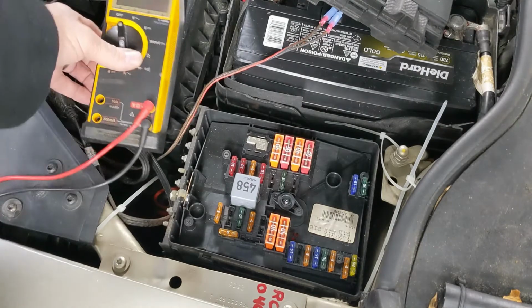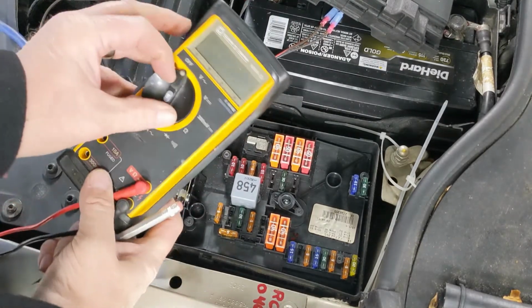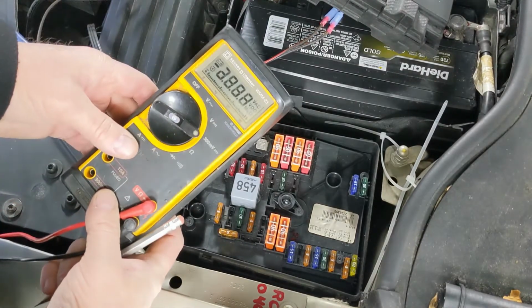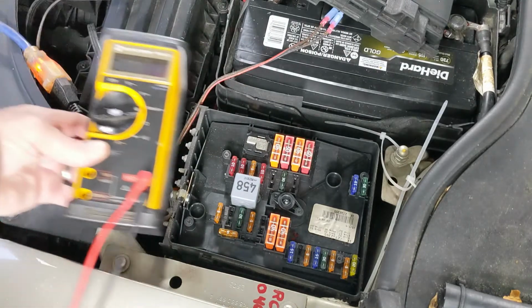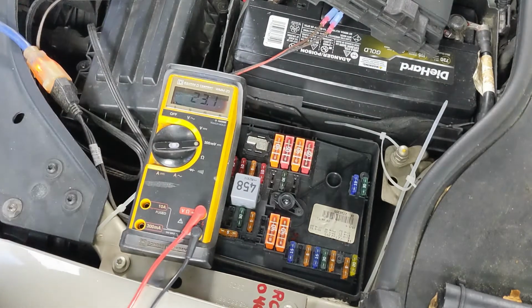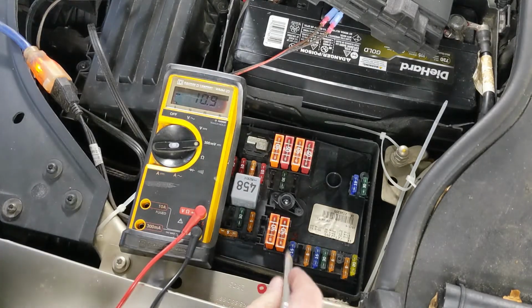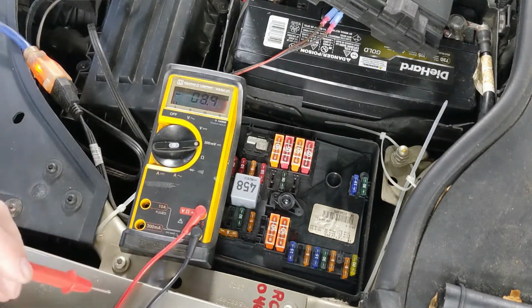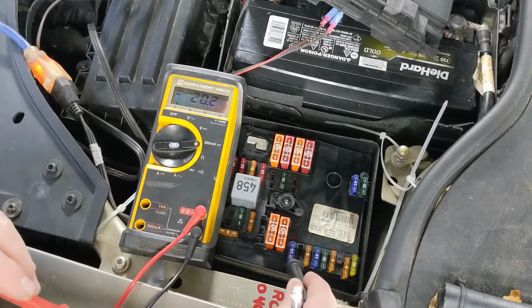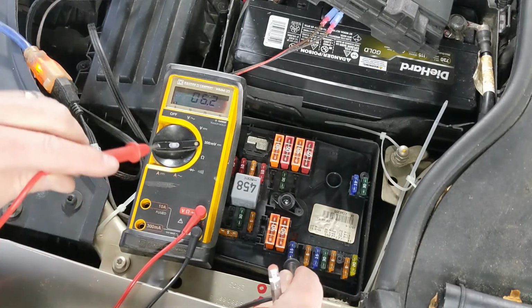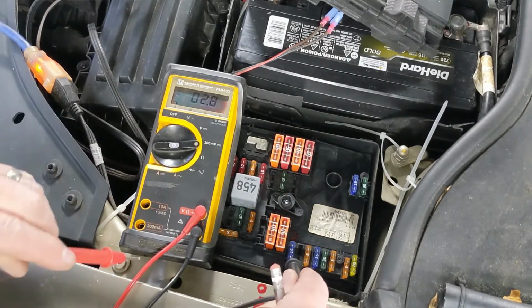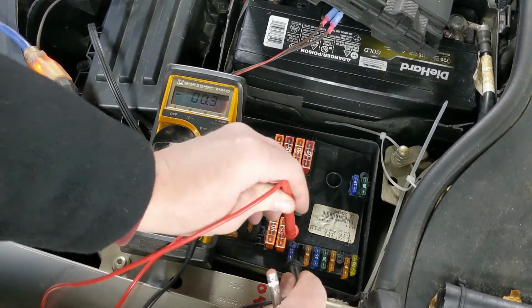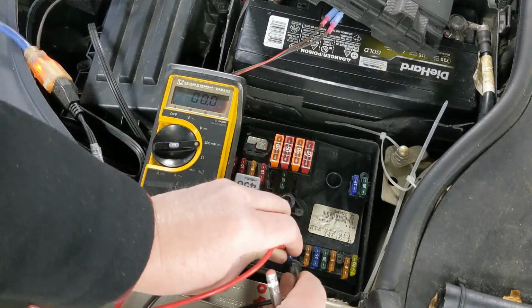So what I do is I have a voltmeter here, and I set it to the millivolt scale. I'll take this one of the fuses where I was reading a large amount of current on it. You can see when you put one probe on there, you get a lot of reading. It's just picking up noise, so you have to make sure you're making good connection with both connections.